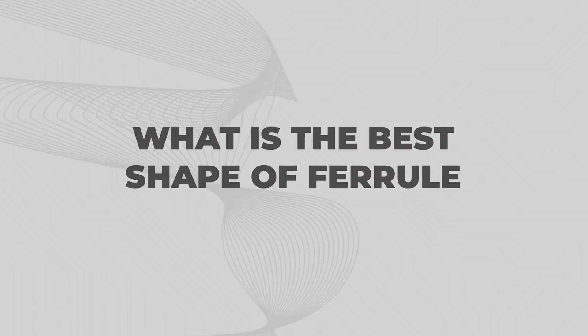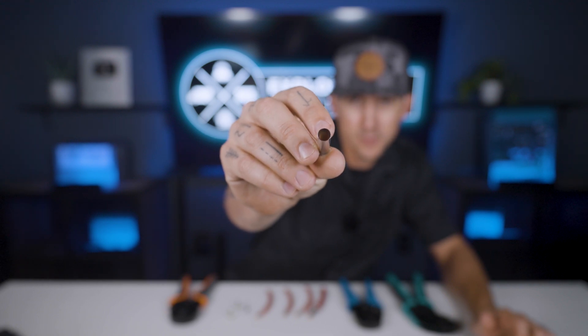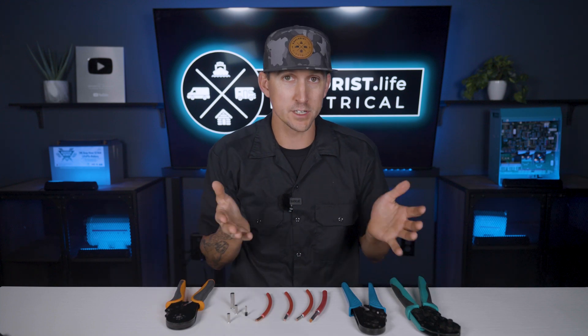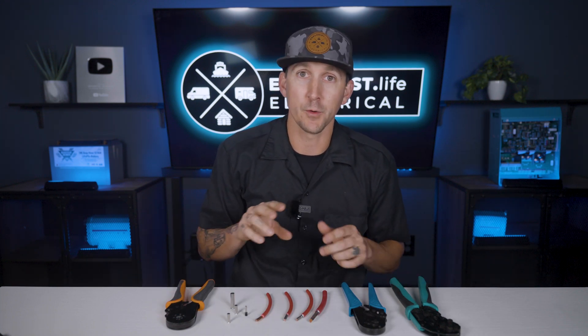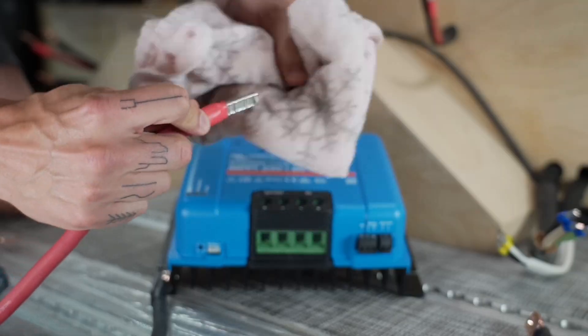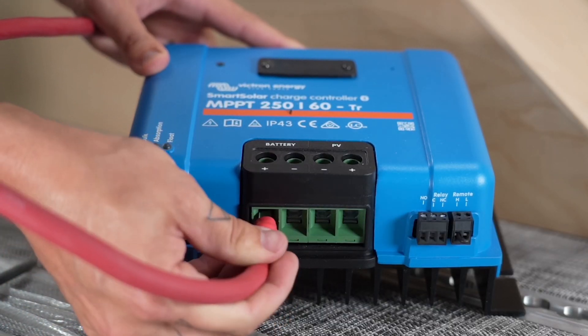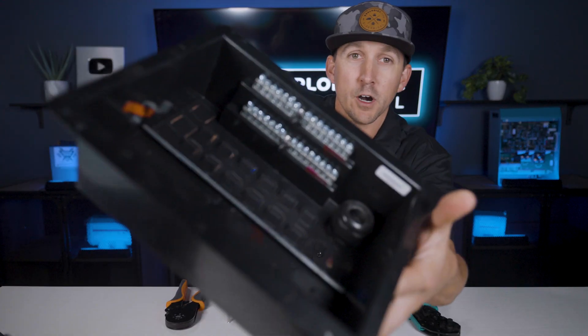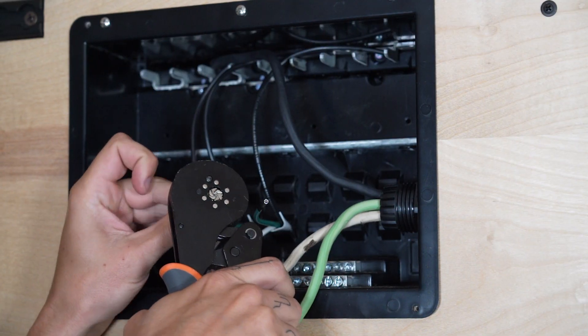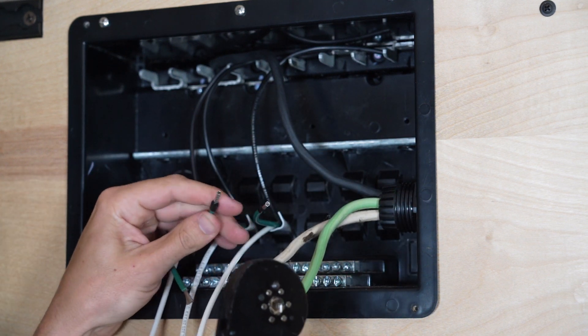What is the best shape of ferrule? All ferrules are round to start and they take their final shape based on the crimper used, but how do we know which crimper to use? We can simply look at the terminal that we're connecting the wire to, see what shape the terminal is, and then use the appropriate crimper to make the same shape. A Victron Smart Solar charge controller has a square screw terminal so it needs a square shaped crimp. The bus bars in the bottom of a 120 volt AC distribution panel have round terminals so it needs a round shaped crimp.